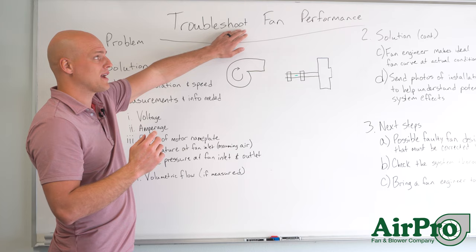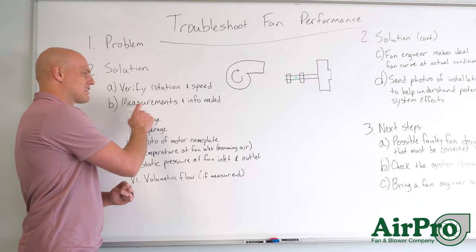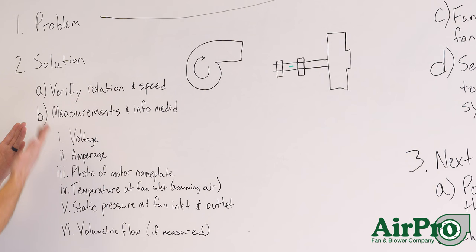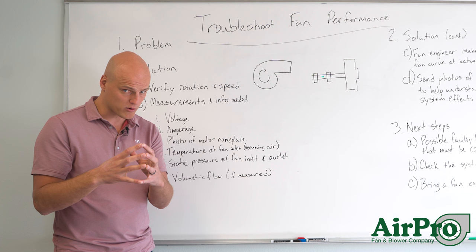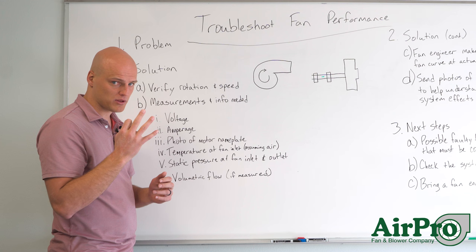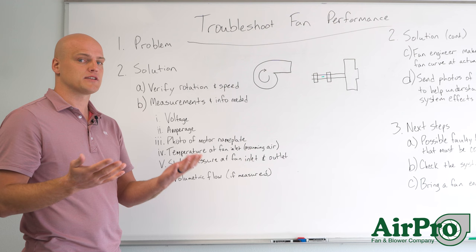If you've verified rotation is good and speed is accurate but you're still having a problem, we move on. These are the measurements and information most commonly needed. The horsepower being consumed from the motor does not lie — we love getting horsepower information. We ask for voltage input to the motor, amperage off the three legs on a three-phase motor, and a photo of your motor nameplate. We use these three bits of information in a calculation to figure out your motor horsepower, and we're going to relate that to the fan curve.